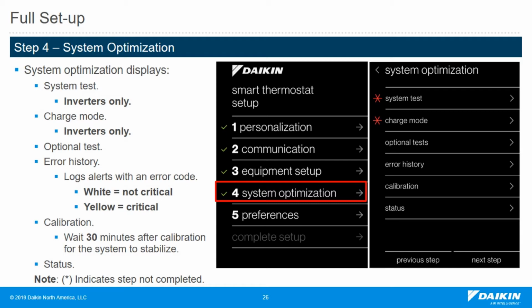You'll also see charge mode on this screen. This allows the inverter to run at a stable rate, high speed, although it may seem it goes from medium to medium, high to high. It is a stable state and allows you to check the subcooling. So you can connect to it and look at the subcooling, but only in the charge mode. Keep in mind when you enter charge mode, you should have the system off. Should not be operating heating or cooling. And then enter charge mode. It will run on its own for an hour and leave charge mode, but it will return to the system off. So if you are completed with checking your subcooling and you want to turn the cooling back on, you'll have to go in and exit the charge mode and go back into cooling.